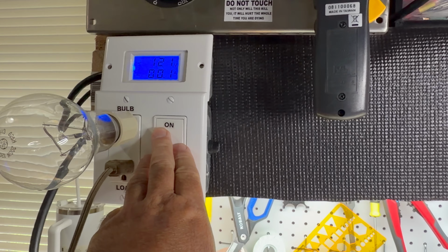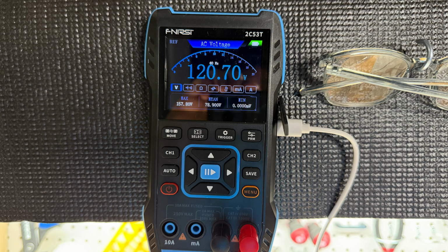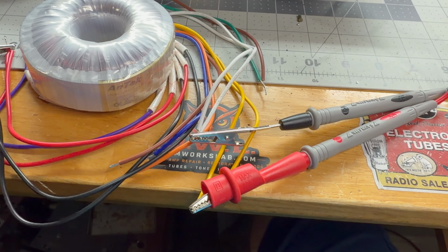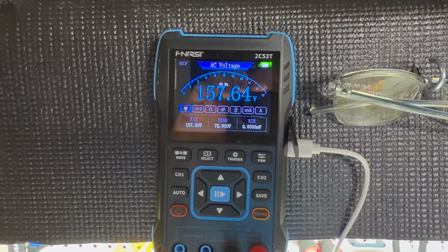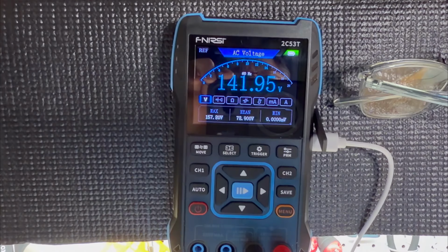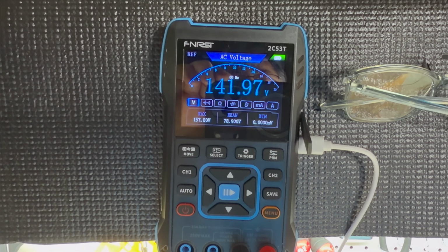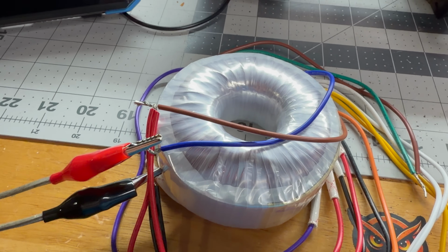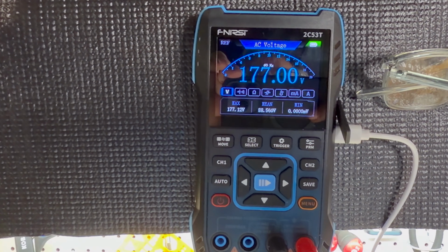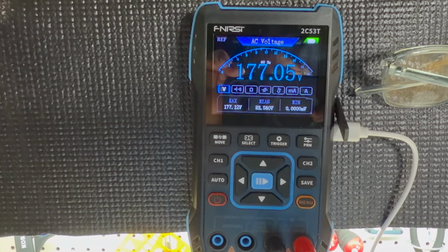First, let's just measure our normal voltage at the primary: we get 120.7 volts. Then we measure the voltage at the secondary: we get 157.6. With the heater winding in series with one leg of the main, we get 142 volts. And then if we reverse the heater windings, we get 177 volts.